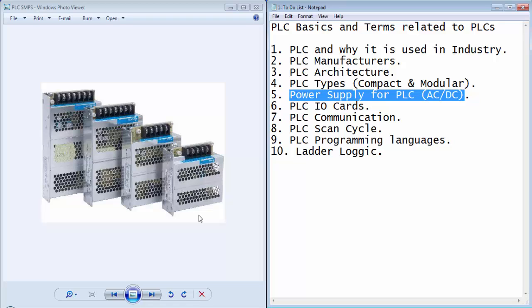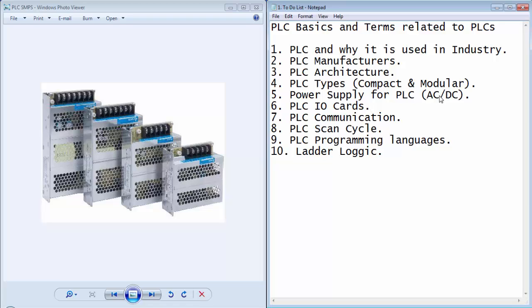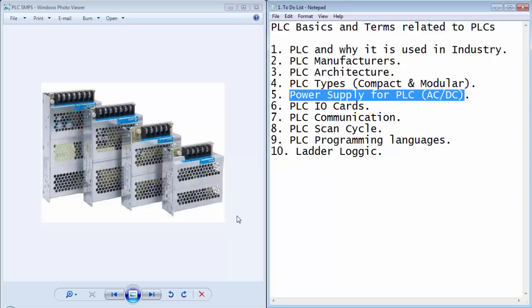There are two options to provide power to a PLC device. We can either provide AC 220 or 120 volts, or 24 volt DC, but again it depends upon the PLC type. If PLC system requires a DC supply, then we have to use a SMPS to convert 220 volt AC into 24 volt DC.